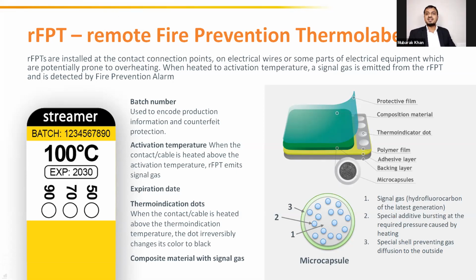This rFPT has a batch number, and it has 3 temperature indications, as you can see on the screen: 100 degrees Celsius, and we have 50, 70, 90. The 100 degrees Celsius is the activation temperature. This is the temperature at which the sticker will get activated. And then we have 3 pre-indication dots at 50, 70, and 90.